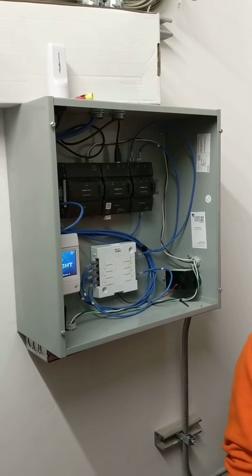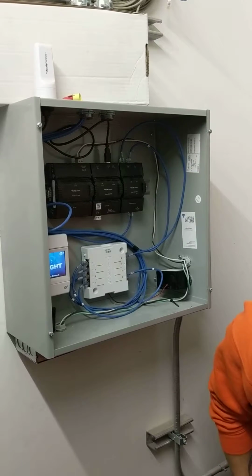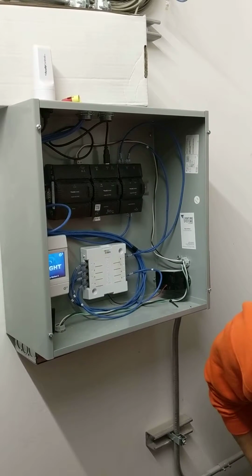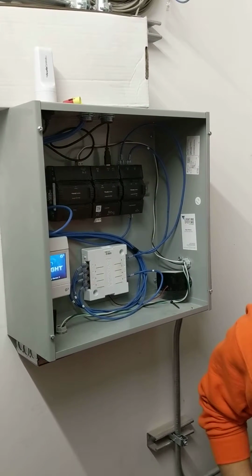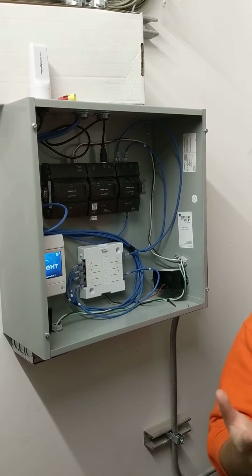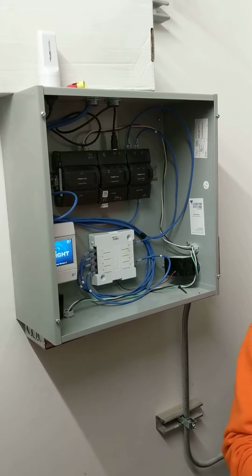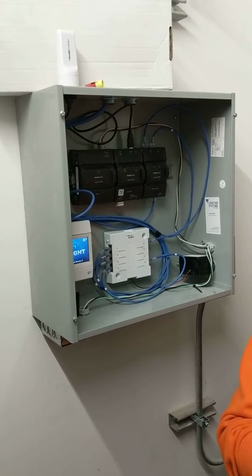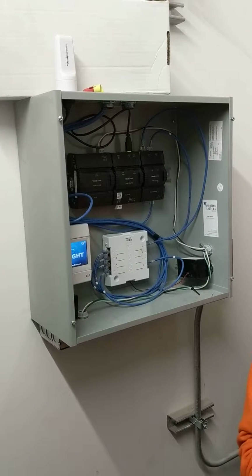I'm just thinking if they have a presentation or something going on, they want the lights off at 1 p.m. Can they go to the switch and turn it off? Absolutely. The switch will turn it off. It'll close off the sensor. The switch will override everything. The occupancy sensors, per code now in Ohio, are only there to turn lights off. They won't turn them back on.